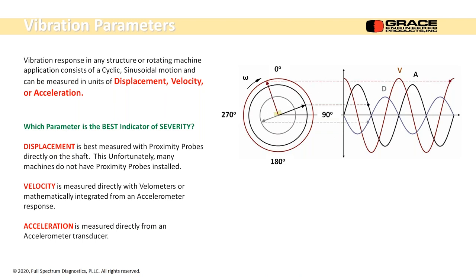The probes are inserted through the bearing housing and come really close, within about 30 to 50 mils of the shaft. They have a magnetic flux that changes with shaft motion, so they're able to detect thousandths of an inch. Really tiny measurements, tens of thousandths, and it's real detailed.